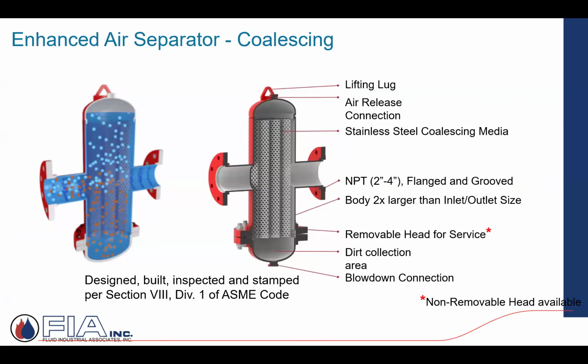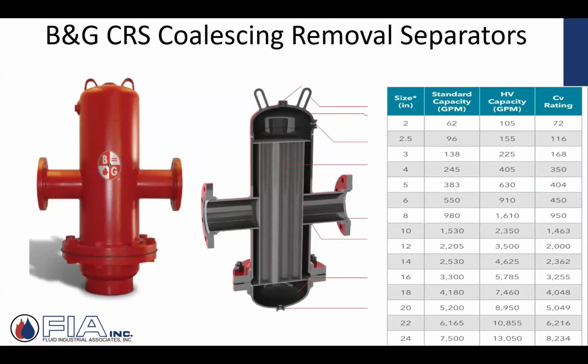Commercially, it would look something like this. Again, ASME rated, very effective, perhaps on the pricier side of technology, but very effective at separating air from the pumped flow. So that would be the commercial version of what we'd call the lighter commercial or residential air separator, coalescing. That's just a spec sheet, if you will. Pretty impressive in terms of flow rates as you get into some of these larger commercial settings. In what size? 2-inch all the way up to 24-inch. I haven't seen a 24-inch live in person. Will, I don't know if you've bumped up against it, but I'm imagining it's like the size of a refrigerator or somewhere in that range. It's quite impressive.